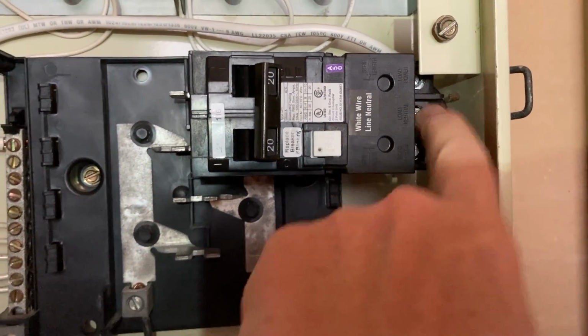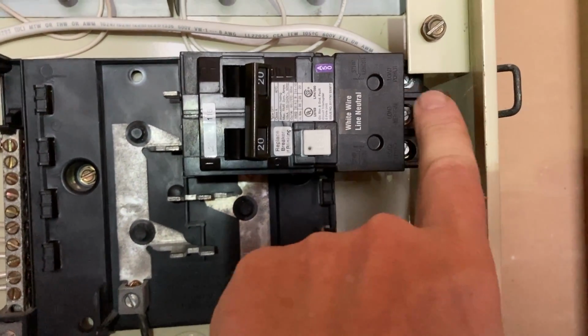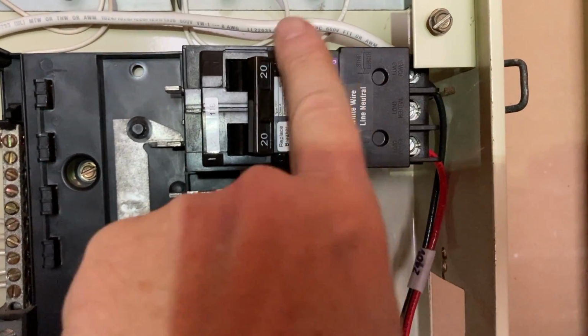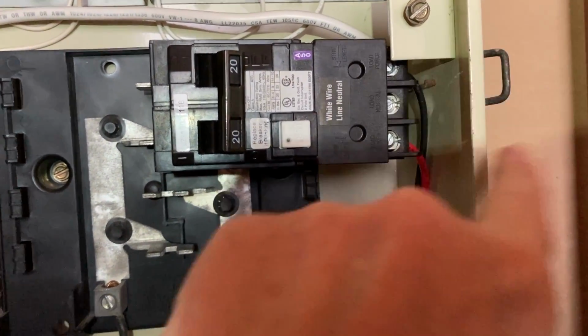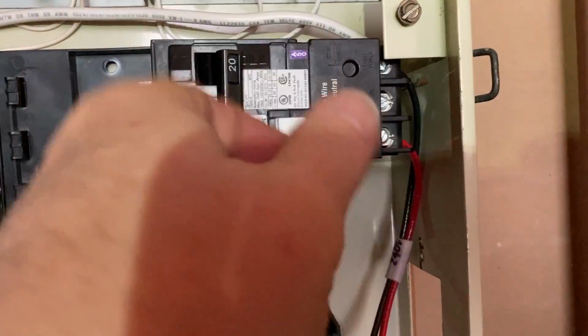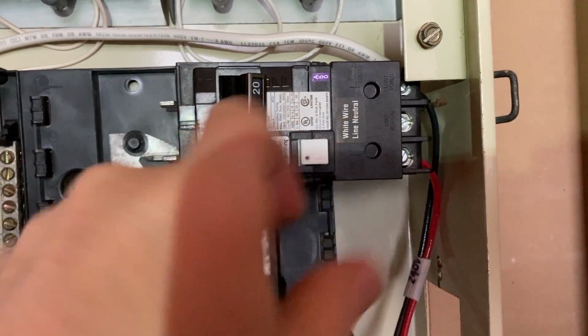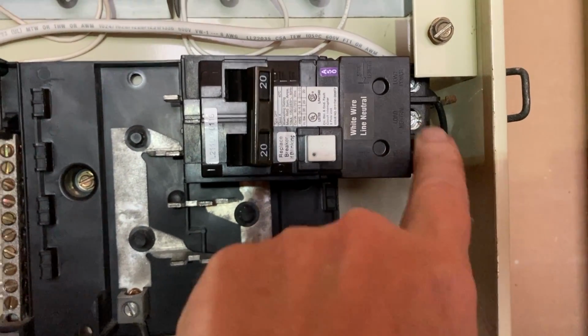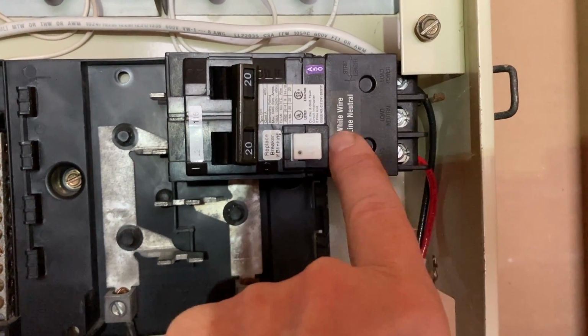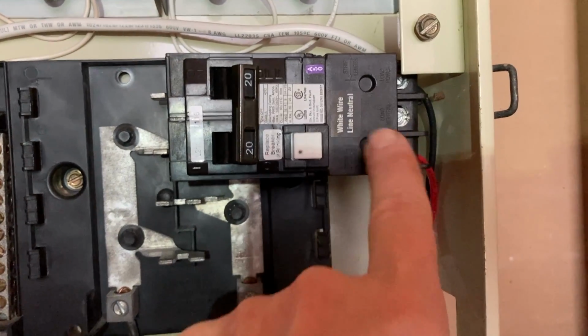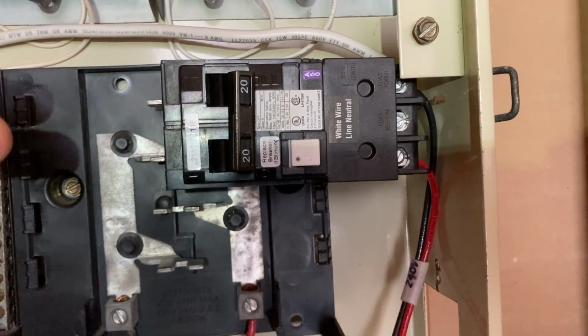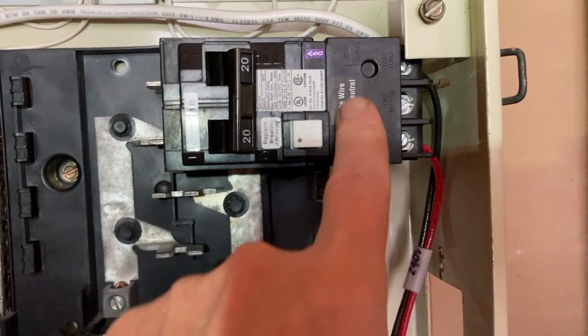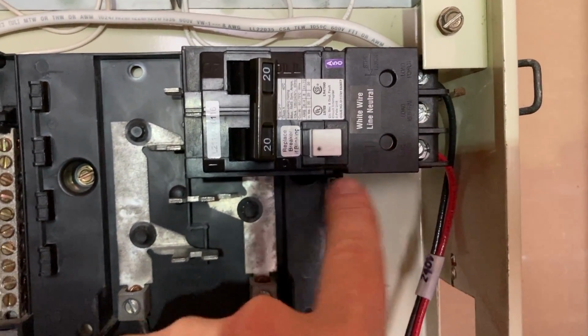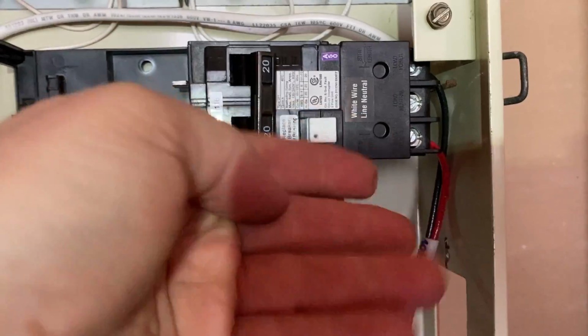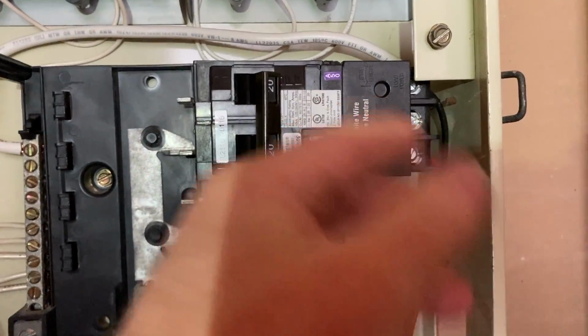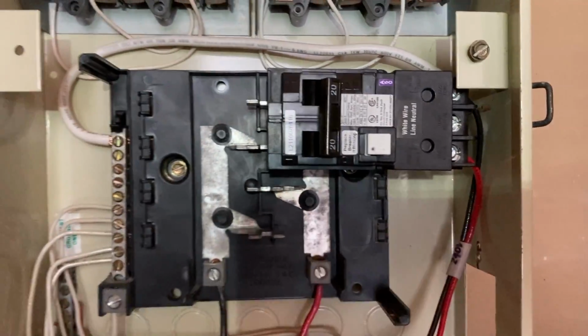You can run this with or without a neutral, because if there's no neutral, the current going out on one leg comes back on the other, and that reverses 60 times a second. But the currents will always cancel close to 0. If there are some 110 loads out there as well as a 220 load, then some current comes back on the neutral wire. The hot leg and neutral going back to the transformer will be canceling out the leg that's feeding, and this is always changing 60 times a second. What it's really doing is a vector addition of the currents trying to get to 0. Anyway, I hope that makes sense.